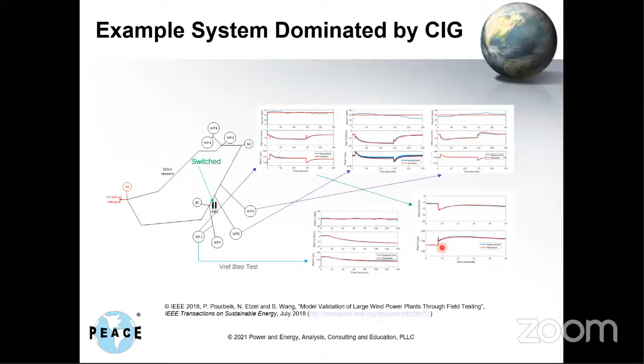Here's an example of large signal response—this is a battery, EMT versus positive sequence. For balanced faults, you get a very good match across the board. For unbalanced faults, you don't get as good a match, particularly in Q. Why? Because one model is positive sequence and the other is EMT, and positive sequence, at least right now, cannot capture the negative sequence components and whatnot, so it can't really emulate what the controls are doing.